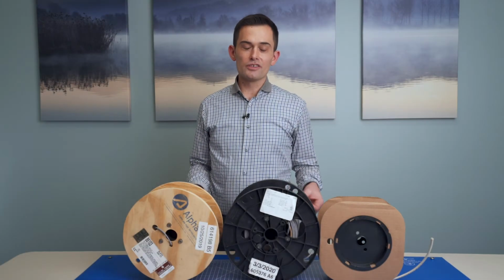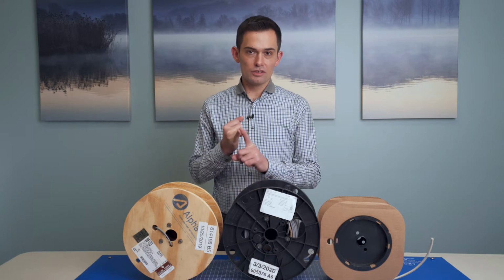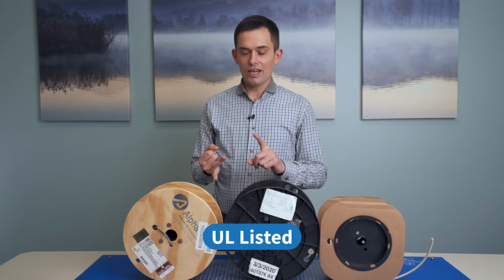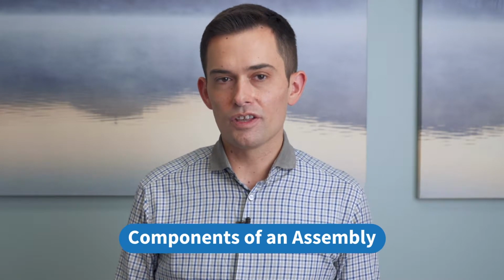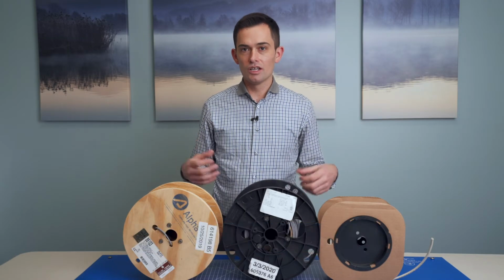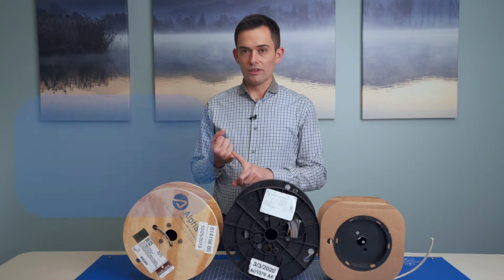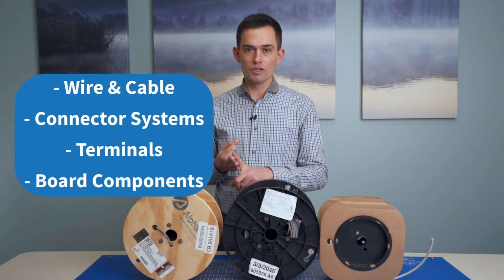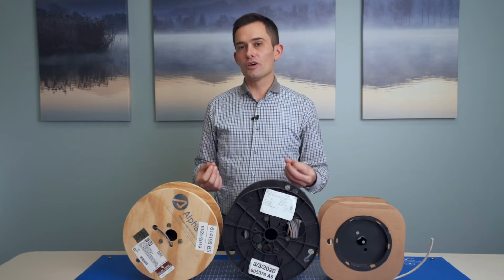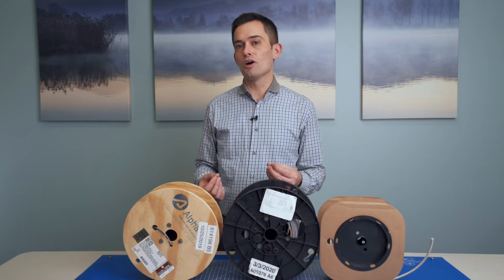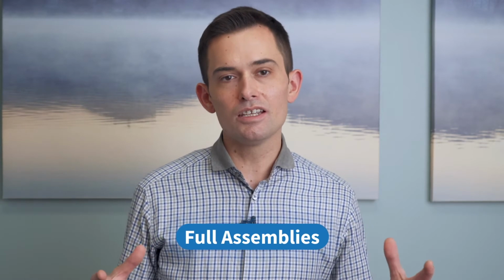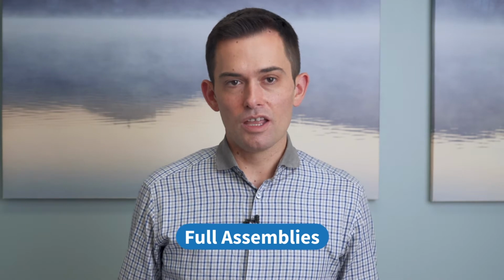So in the context of cable assembly, you'll run across terms such as UL listed and UL recognized. When you see the term UL recognized, it's usually referring to raw components that make up part of something larger. So things like wire and cable, connector systems, terminals, board components, all of those might bear the UL recognized component marking.